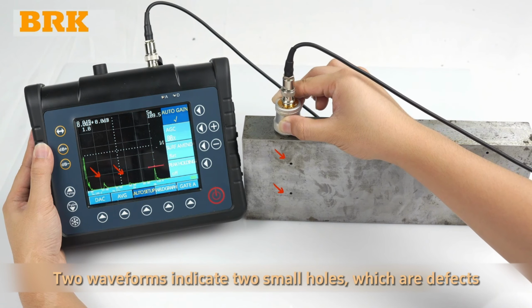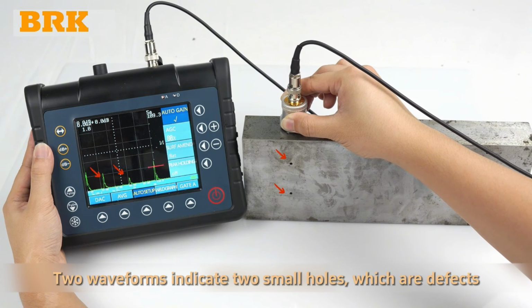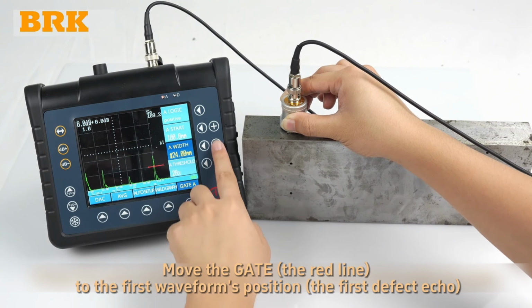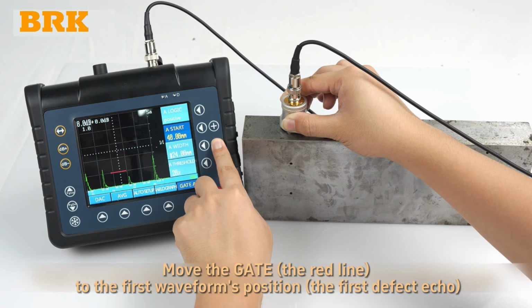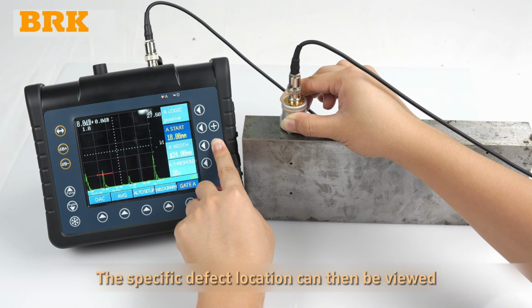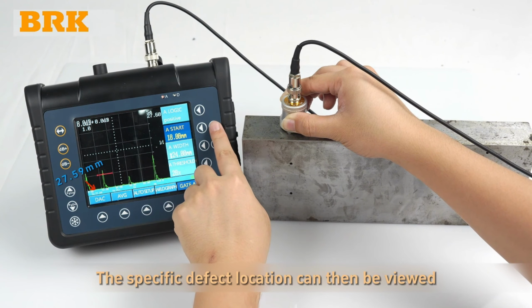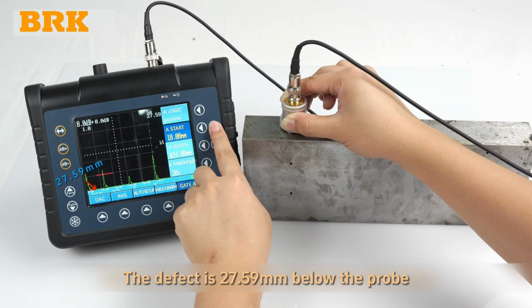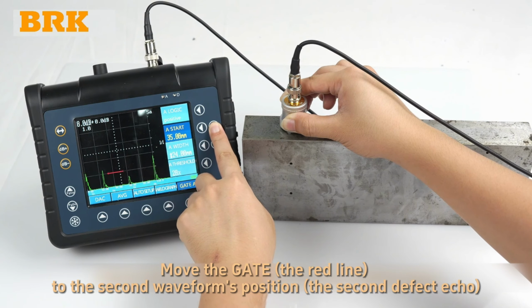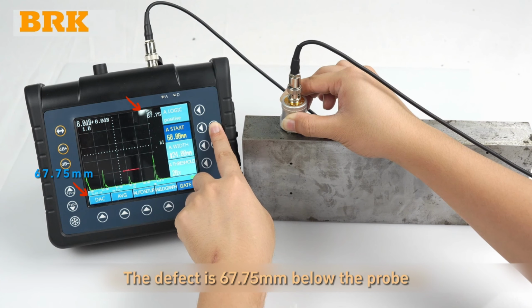Waveforms appear. Two waveforms indicate two small holes, which are defects. Move the gate to the first waveform's position. The specific defect location can then be viewed. The defect is 27.59 mm below the probe. Move the gate to the second waveform's position. The defect is 67.75 mm below the probe.